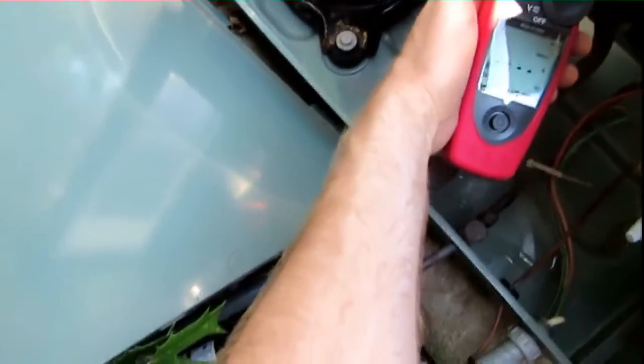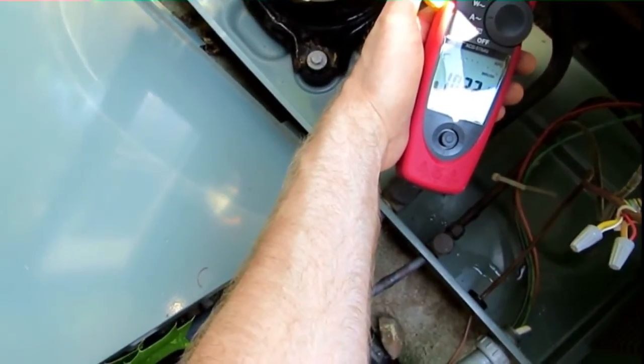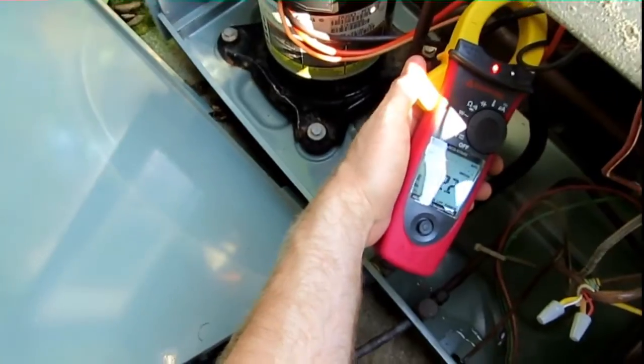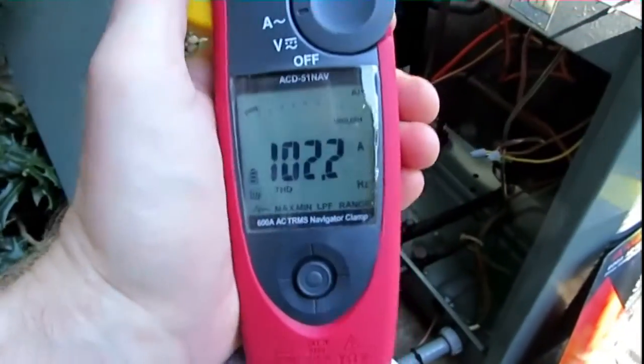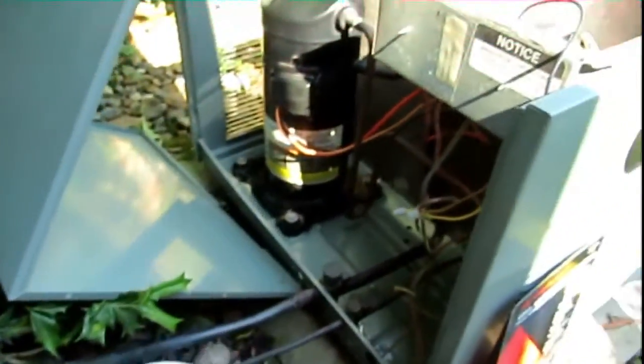Keep the hat cam on — hopefully this will show up. I'm going to push the test button. Got it on. So we got 102.2 amps — that's without the 521. Now I'm going to wait a minute and then do a test with the 521 reconnected.